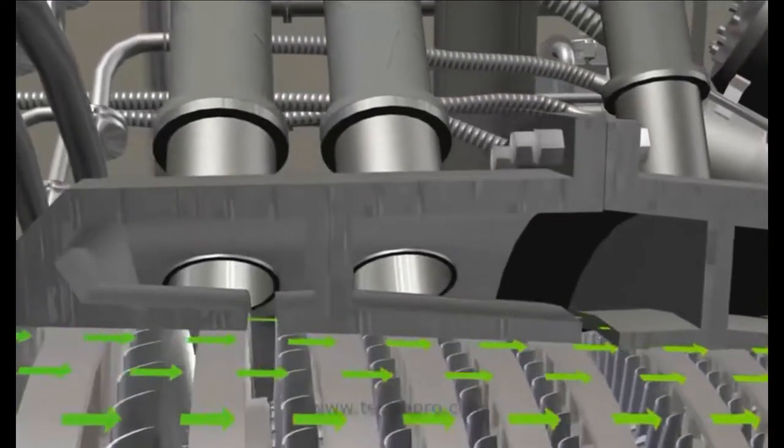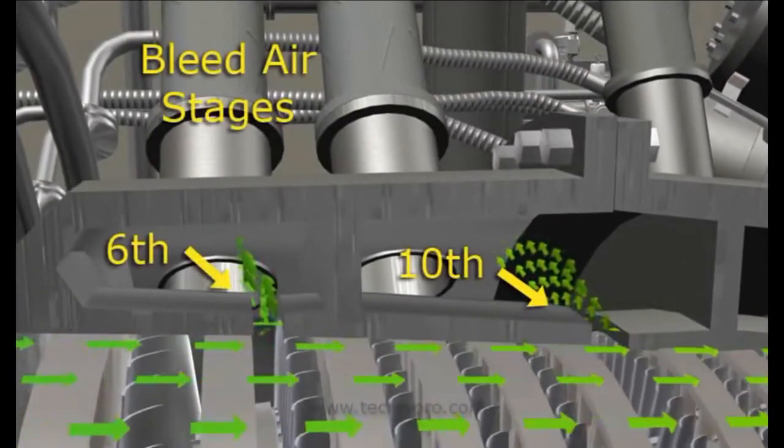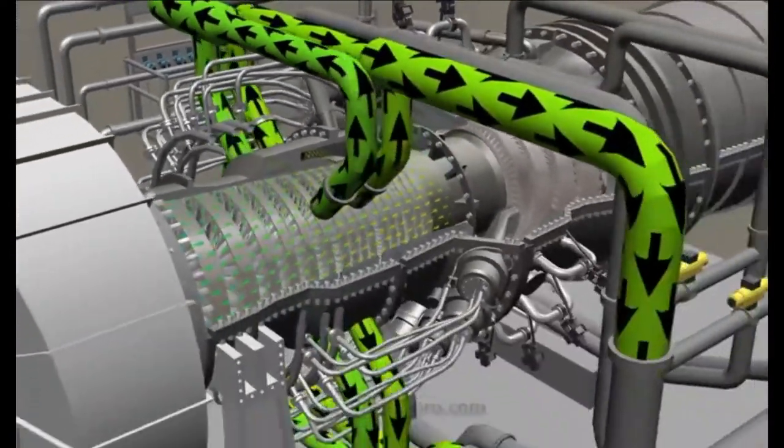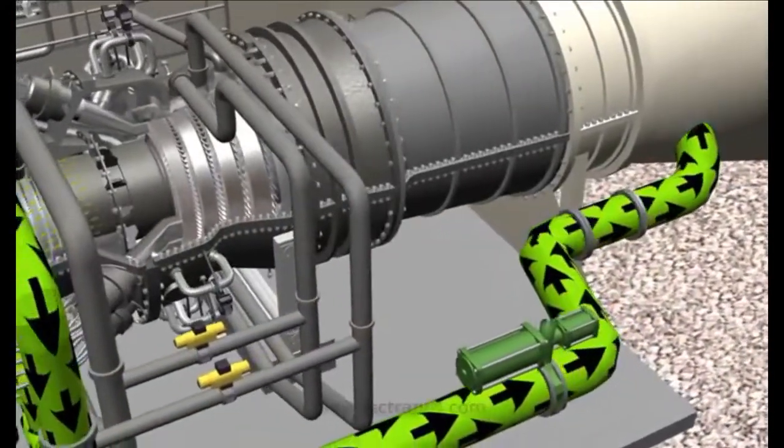During startup and shutdown, air is extracted from the sixth and tenth stages of the compressor and is bled to the turbine exhaust. This will help prevent compressor surge and blade stalling.